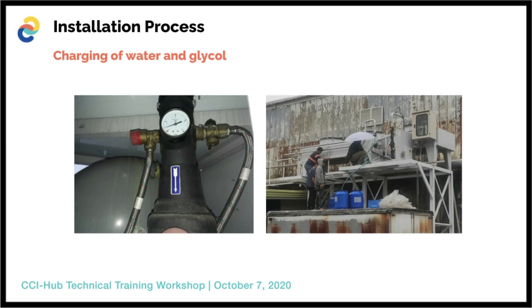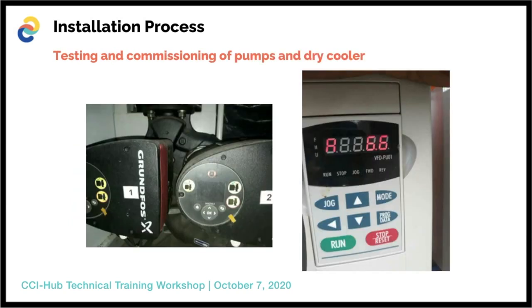And the next procedure is testing and commissioning of pumps and dry cooler. As you can see in the picture, on the left side, this is a Grundfos Magna twin pump, which is programmed to auto-adapt settings for cut-in and cut-out operations depending on the needed load demand, with a 12-hour rest interval on each pump motor. This is a fully inverter pump motor with variable speed controllers. On the right side of the picture, you can see the VFDs in the dry cooler. This is also programmed to run about 0 to 80 hertz with a liquid temperature controller with automatic and manual functions in case the VFD fails to run.